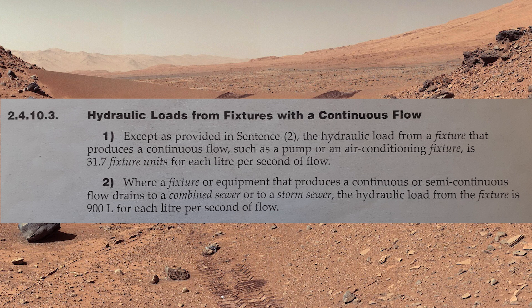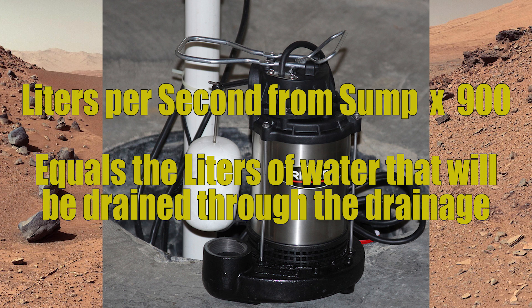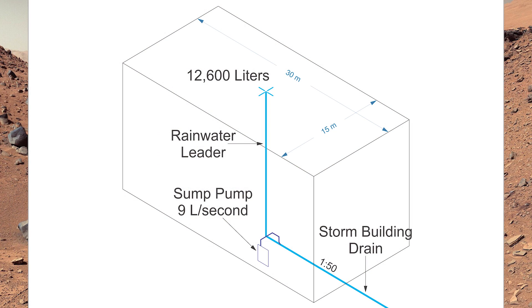Simply put, a fixture that produces a continuous or semi-continuous flow is a sump. We need to find out how many liters per second will flow through the sump so we can multiply that number by 900. That will tell us how many liters we will dump into our storm building drain — or according to this clause, a combined building sewer. This building should look familiar from previous videos: a simple flat roof building with 12,600 liters coming down the rainwater leader.